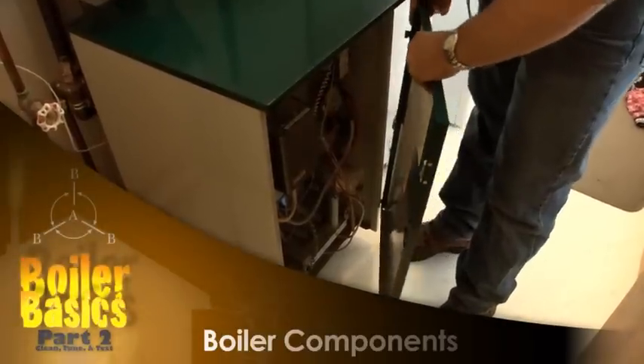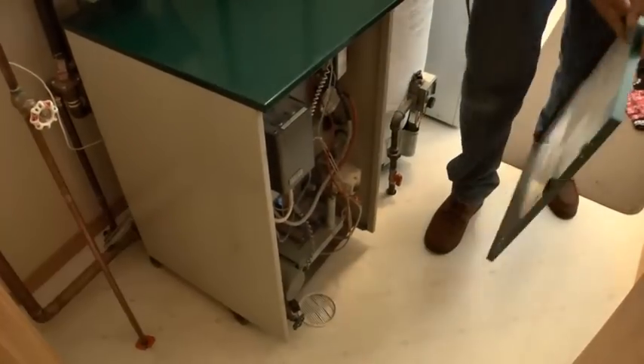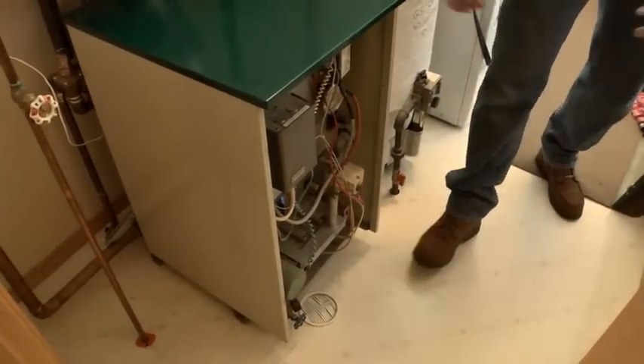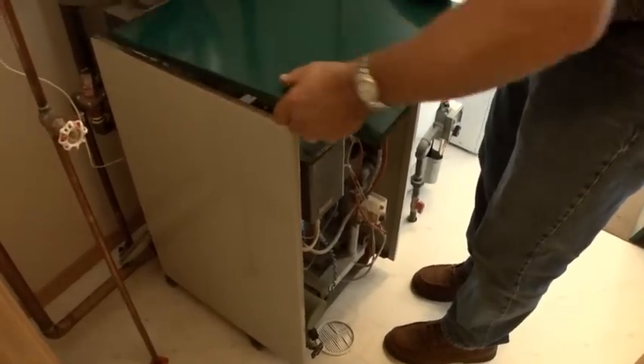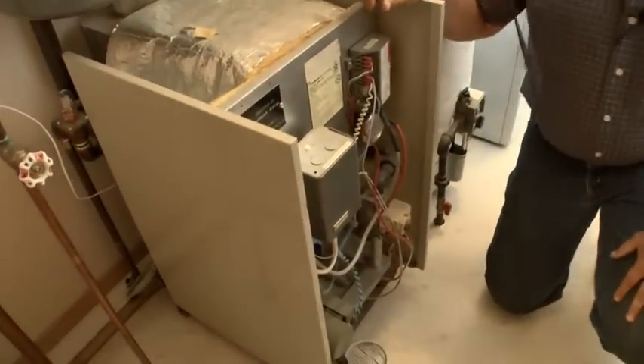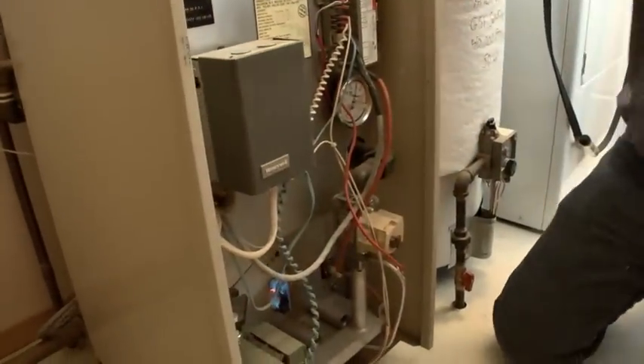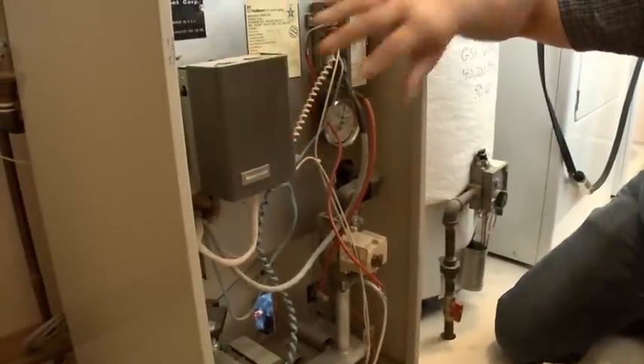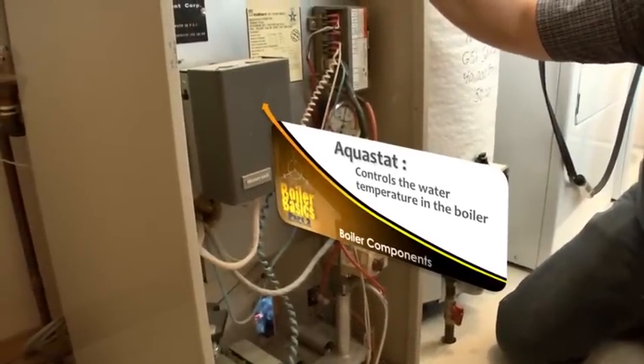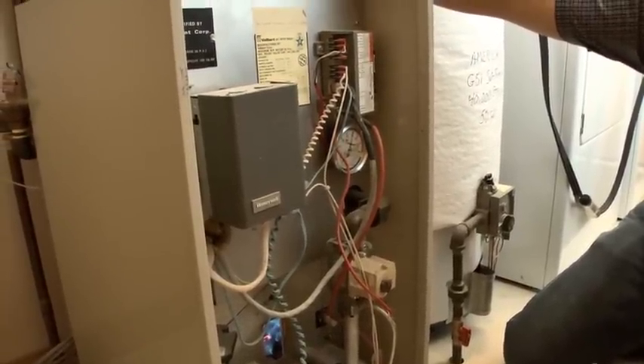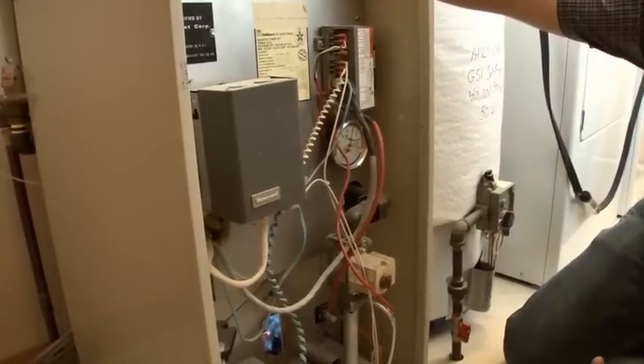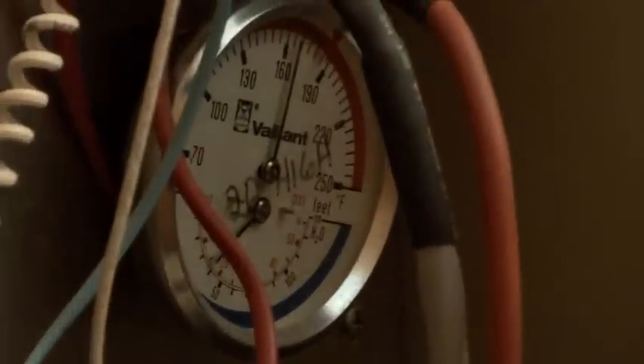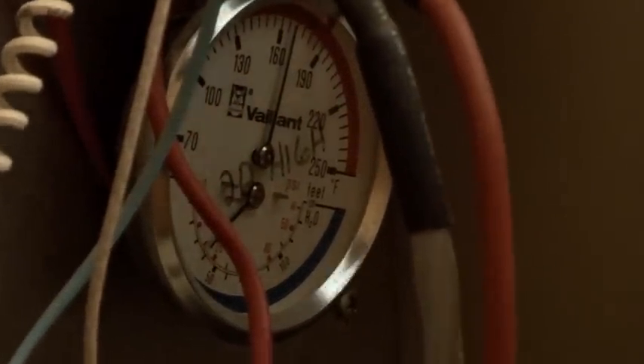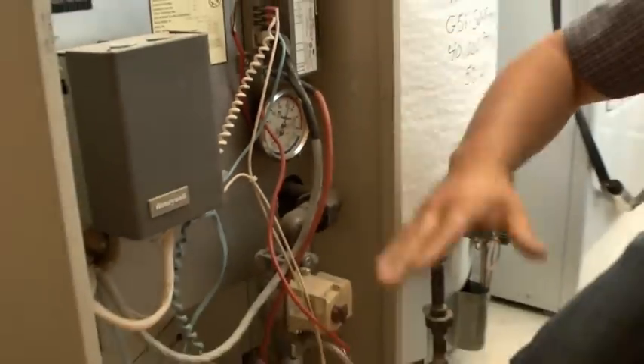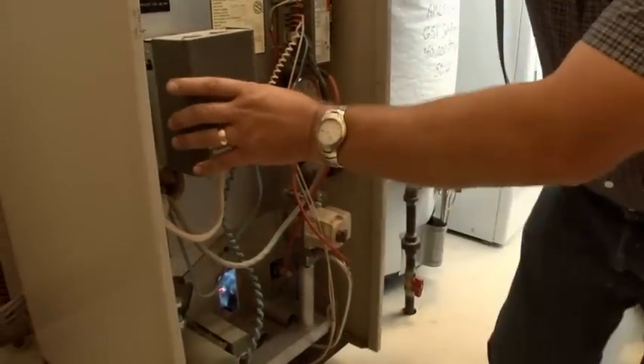Okay, on this boiler, it's pretty easy to take the door off, so I'm going to take the door off so we can look at things a little closer, and even the lid. There's a couple things we want to take a look at. We just took a look at the flames. This right here is the aquastat, and what it does is it has a probe that goes into the heat exchanger, and it measures the temperature of the water inside the boiler. So the boiler cycles on and off, heats the water up, lets it cool down, and then just recycles over and over. And it does that with the aquastat.